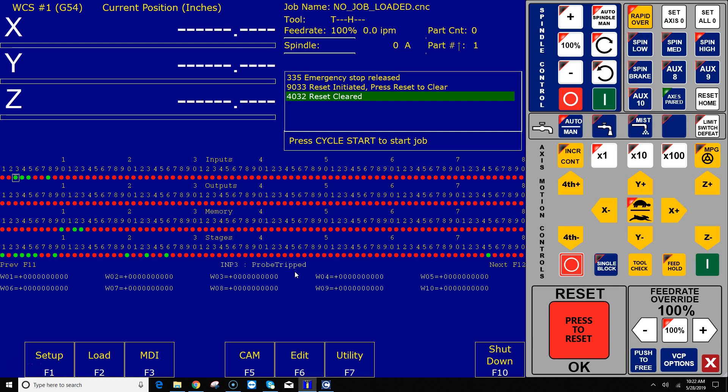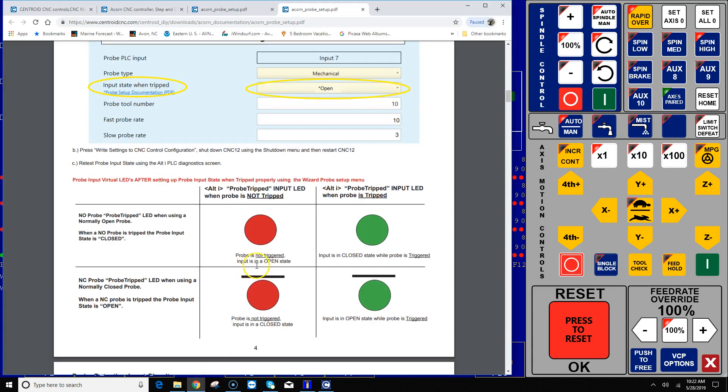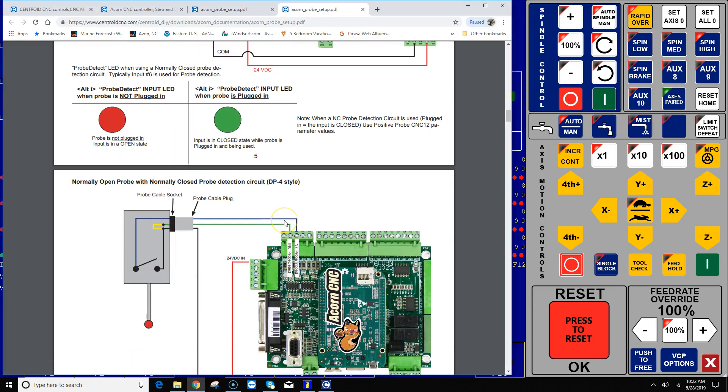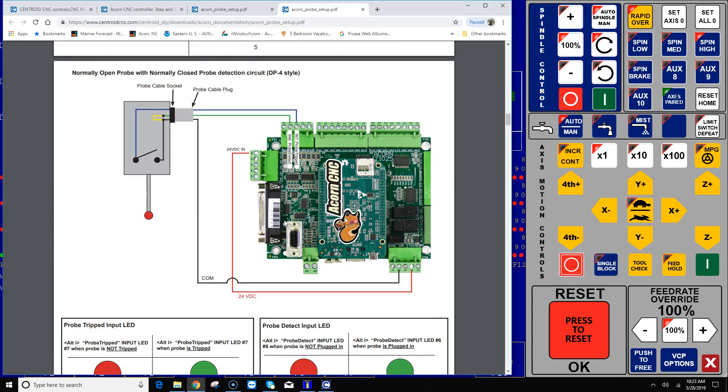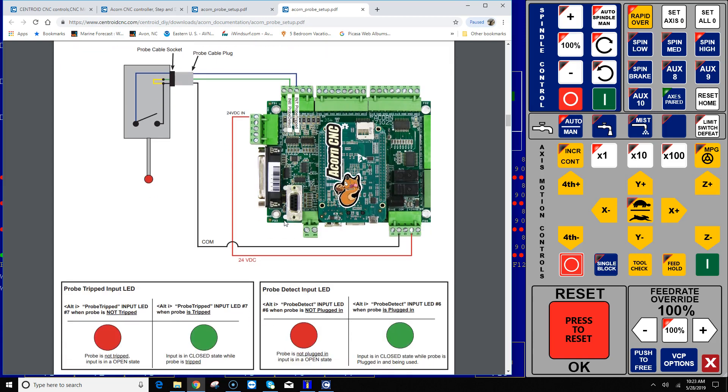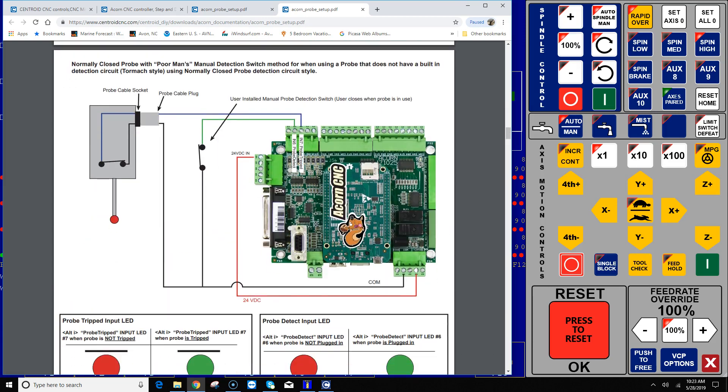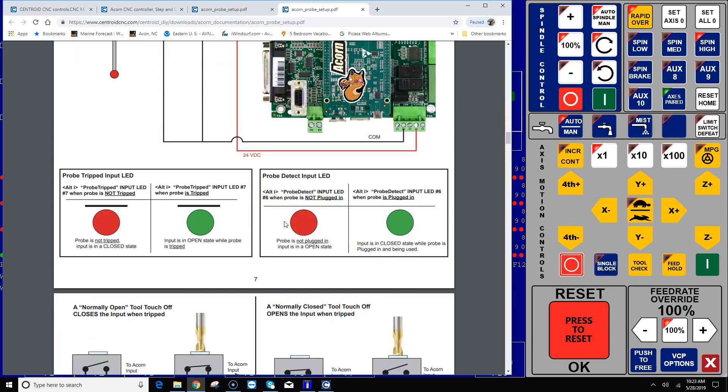I'm not tripped, tripped, not tripped, tripped, not tripped. Let's do the same thing for input six. I'm not tripped right now and I'm gonna trip it. There it goes, tripped, not tripped, tripped, not tripped. And all this is covered again in the probe setup document with some nice wiring diagrams to show you all the typical connections.